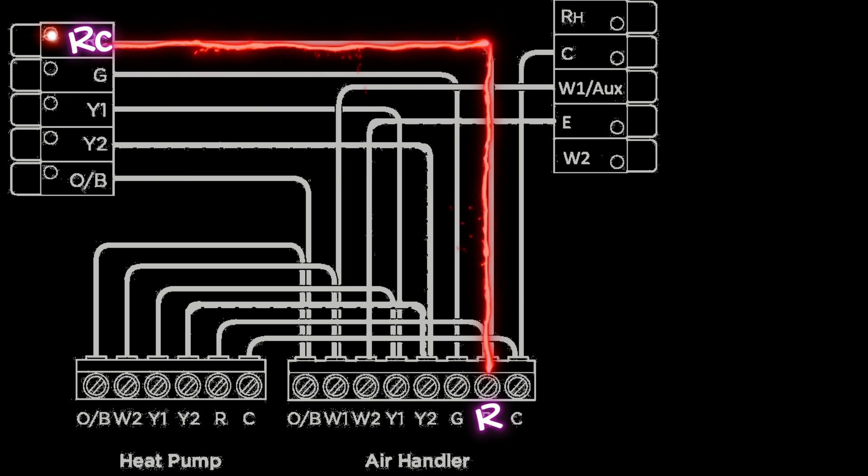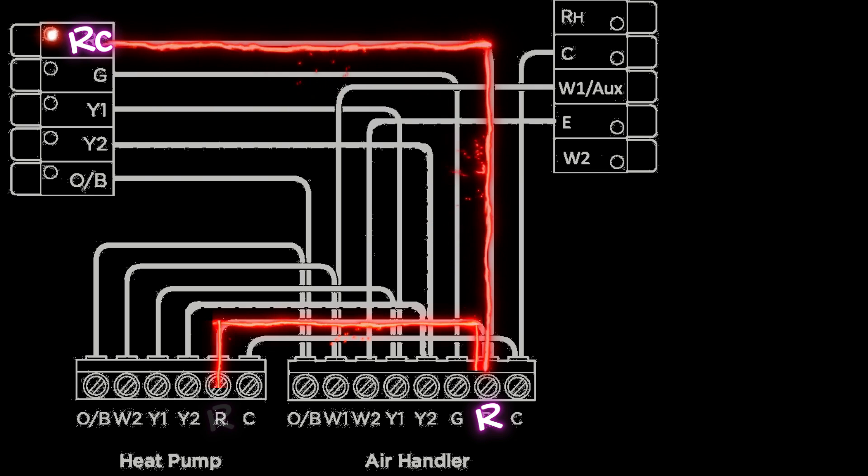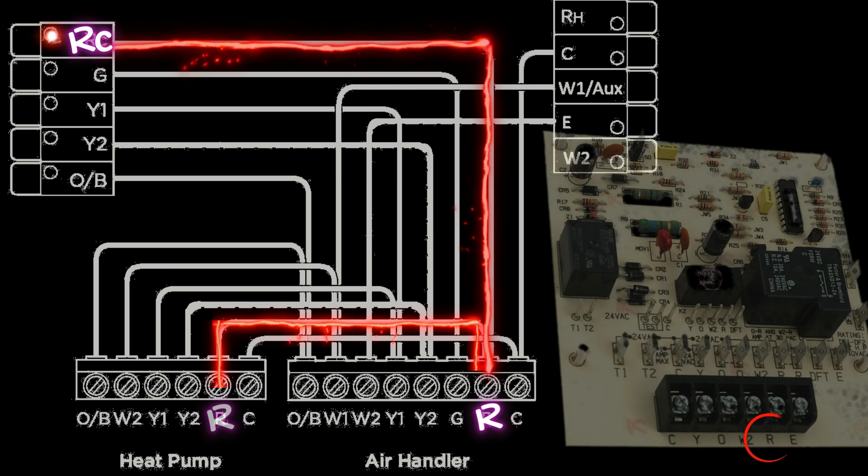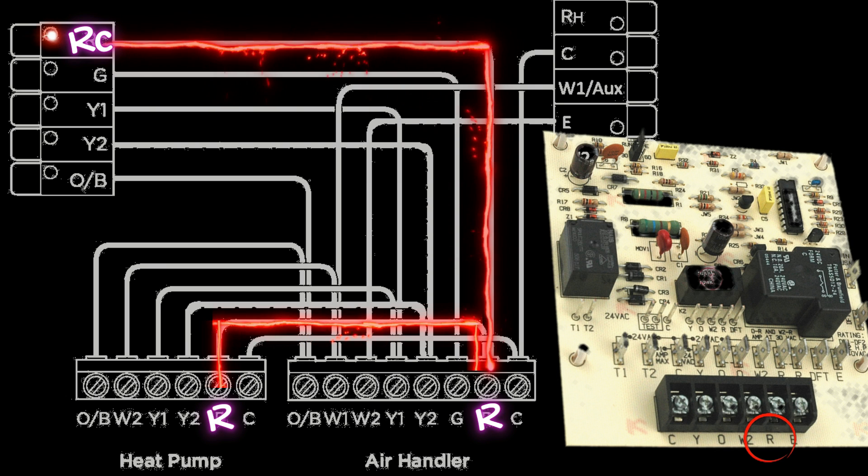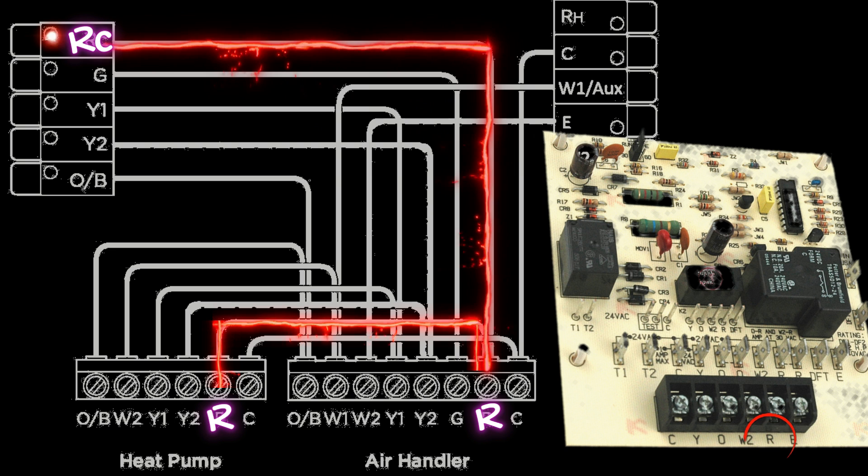Now in addition to this wire coming off the R terminal on the control board in the indoor unit, we're going to have a second wire coming off of that same terminal that is going to go to the R terminal on a defrost control board on the outdoor unit. And the whole purpose of this wire is to power the defrost control board itself. It's an electronic device and obviously needs power to function.